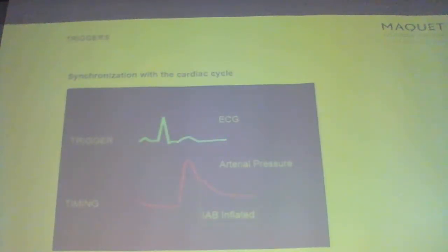Triggers. So how does the balloon know when to inflate, deflate? EKG. A lot of times it's going to be based on the EKG tracing. Your primary trigger is going to be the EKG. The alternate trigger is going to be pressure. It's an art line. It has a pressure in there. It can identify when the aortic valve opens and closes. It can identify those pressure changes, and so it knows when to inflate, deflate. But a lot of times it's going to be based off EKG, which is a nice thing.